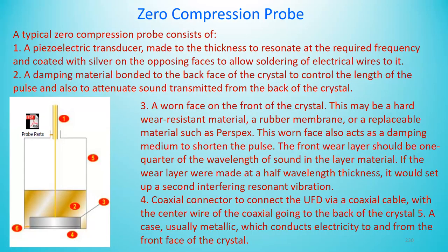A piezoelectric transducer crystal made to the thickness to resonate at the required frequency and coated with silver on opposing surfaces to allow soldering of electrical wires to it. A damping material is bonded to the backface of the crystal to control the length of the pulse and also to attenuate the sound transmitted from the back of the crystal.